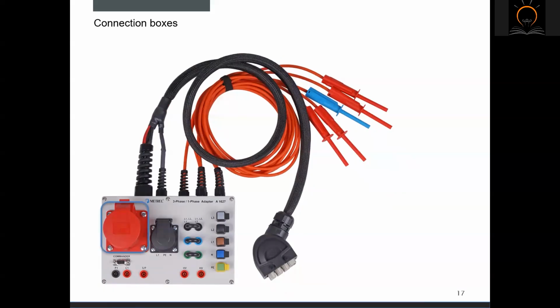We can test three-phase appliances equipped with supply cord, single-phase appliances equipped with supply cord, or equipment intended for fixed installation can be connected as well. This connection box, in comparison to the previous one, enables execution of high voltage test from a separate channel. External test commander for testing of earth continuity or other tests where probe is applicable can be used.